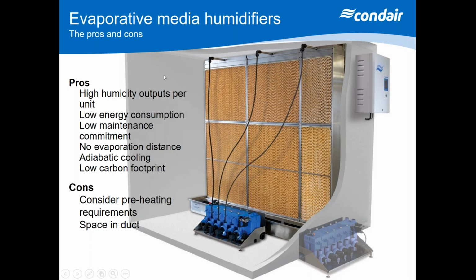Now in most cases you're going to have glass fibered sheets in here, a number of sheets all bonded together to give you what we call a saturation efficiency. So the thicker the media the unit has, the more water it can displace into the air. These units can be anything from 600 millimeters wide up to 7.8 meters wide. We've done big systems. And the duty can go from about 30 litres up to hundreds and hundreds of litres, so very, very high capacity. And this is all being delivered by a pump set that's probably going to be about 0.5 kilowatt. So it's very, very low energy.